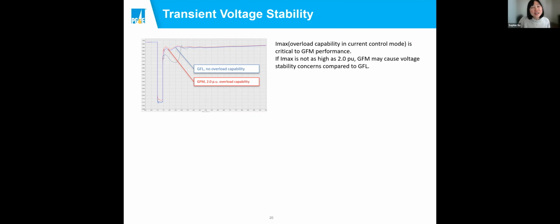Okay, I'll be quick. So I did a quick check of the voltage performance on a network using grid following and grid forming. Initially I got the red and blue plots. They're pretty much similar in recovery, with grid forming slightly better. But there's one caveat I want to put here: the red one from grid forming has 200%, or 2.0 per unit, overload capability. I heard from different sources that it could be possible, but I think there could be cost associated with it. And when we put it into requirements, this 200% overload capability may not be achievable by manufacturers. So I did another test, which is the line in green. I reduced the overload capability from 200% to 125%.